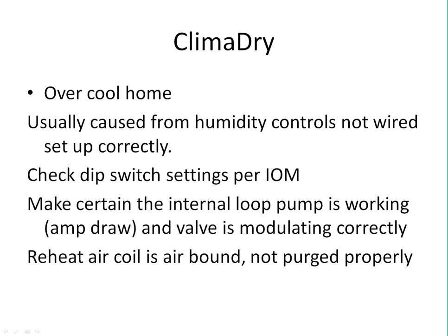As a test, you want to make certain that that internal loop pump is operating in the ClimaDry mode. Again, how do we do that? We take an amp draw on that particular Grundfos pump. Remember, it only operates when it's in the ClimaDry mode. That is also when the modulating internal valve should be operating. It's a very slow-moving valve that modulates and opens up when you're in the ClimaDry mode, which means you're basically air conditioning, but you're shoving some of that warmed loop fluid back up into that reheat coil to keep the air neutral going back into the home. So you want to make sure that that modulating valve is operating correctly.